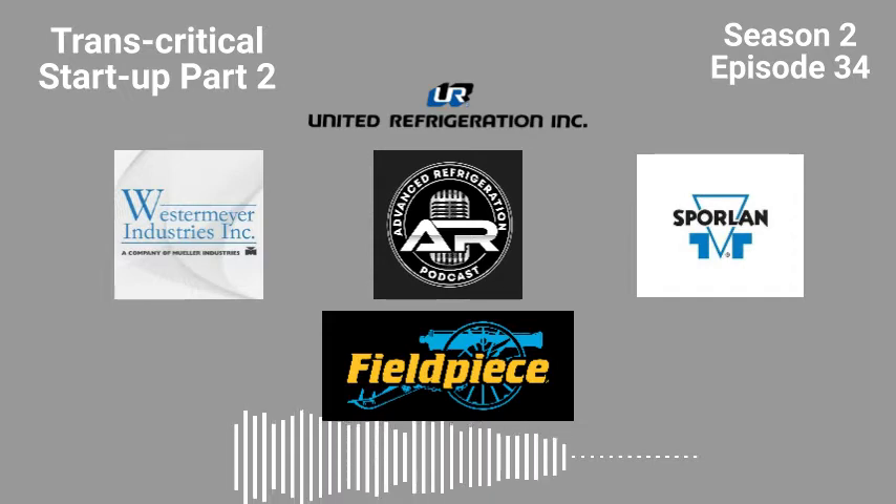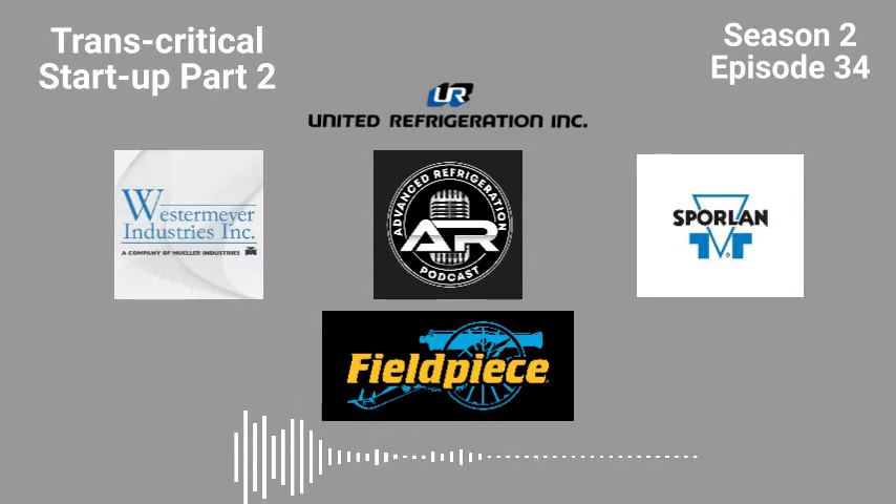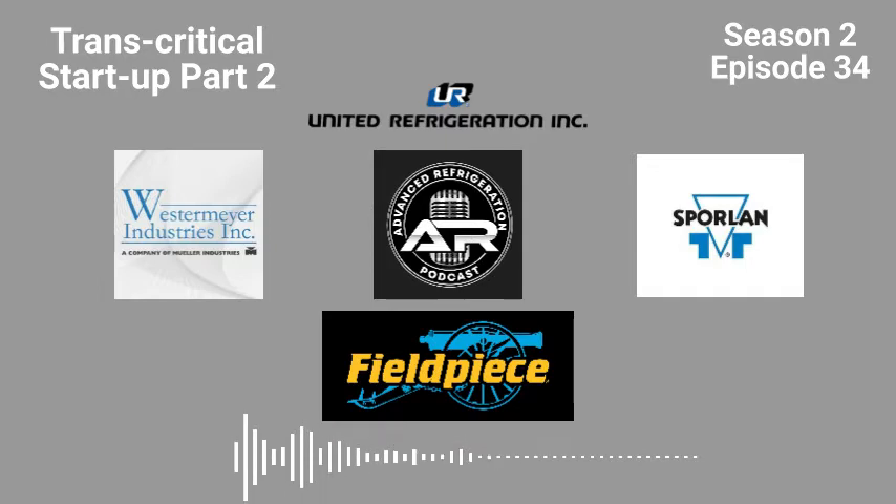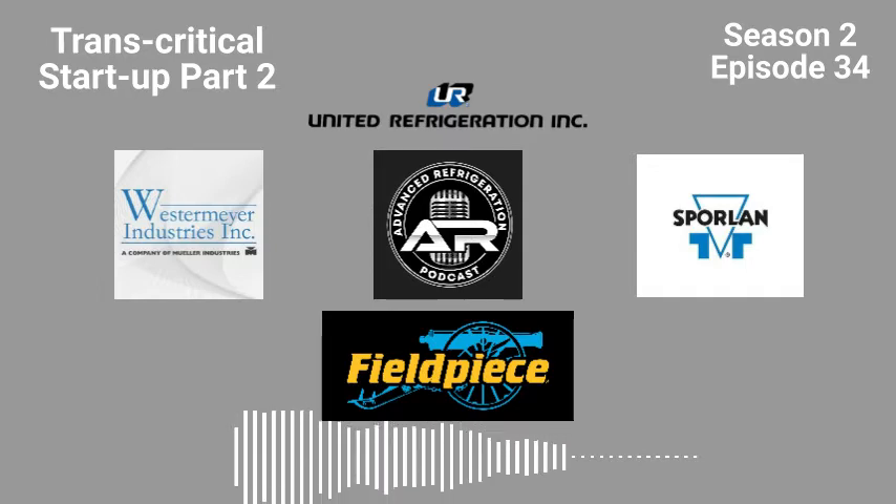You want to either do this with the EMS or switches — if you have switches at the rack, it's amazing, but most of the time you don't. I usually overwrite everything off and then start bringing them on case by case and let them start cooling down. Glass doors, you've got to feather it a little bit. Medium temp is not as bad — it usually cools down pretty quick. I will usually bring the medium temp loads down first so the flash tank isn't bombarding the medium temp suction. I can bring the medium temp down first and then start loading low temp up, so I'm not bombarding the suction.